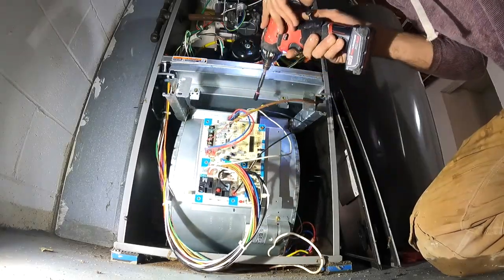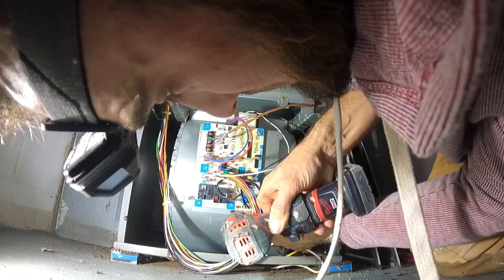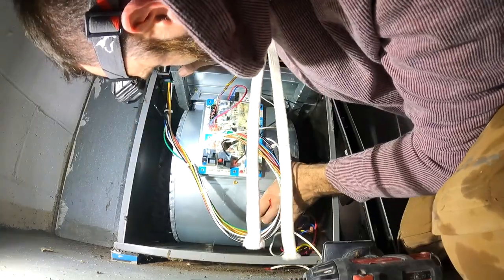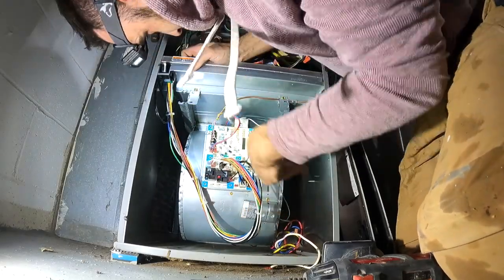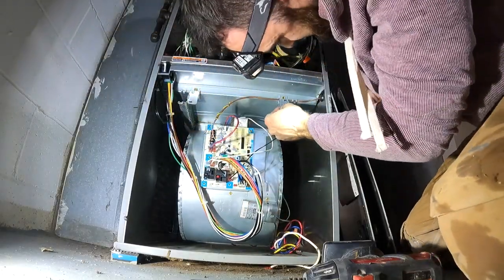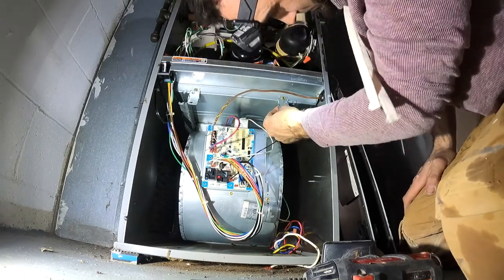Reinstall the electrical onto the motor assembly. There are little guides in there that you have to slide the blower motor assembly on — make sure you get them in the guides. I've messed that up before. Then reinstall the two 5/16 bolts.